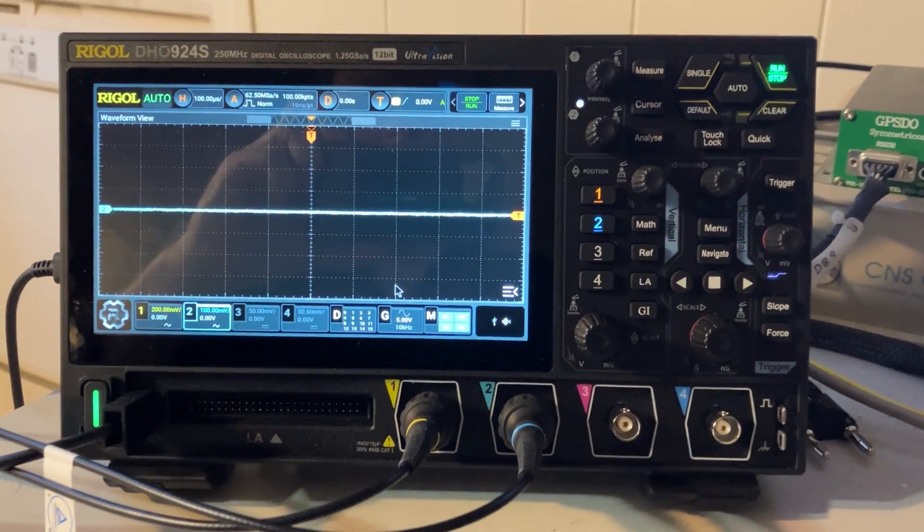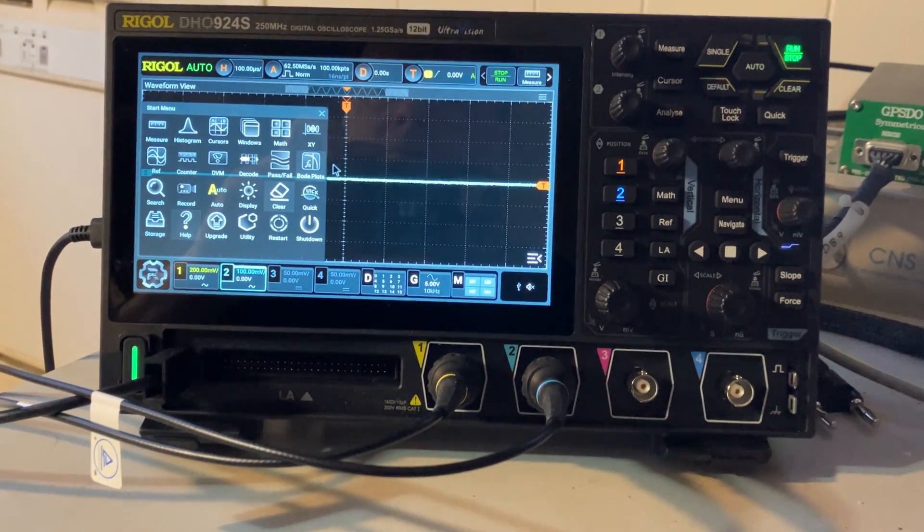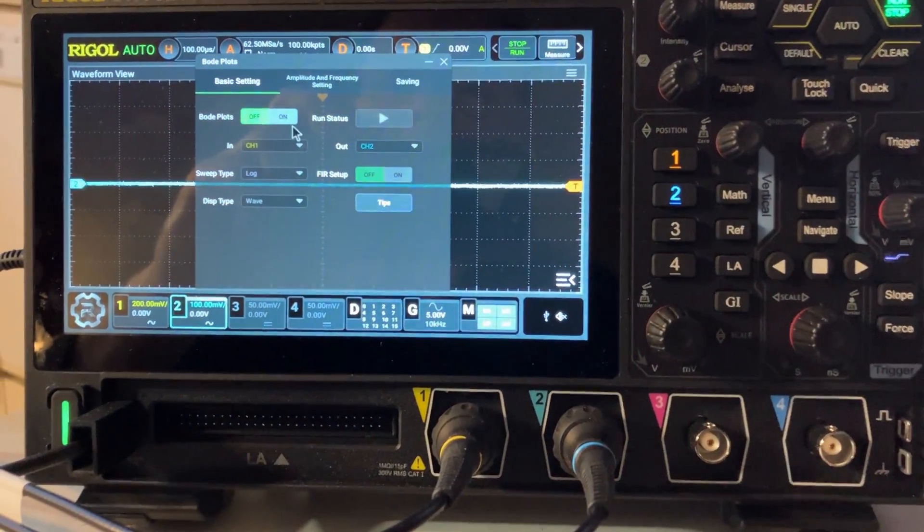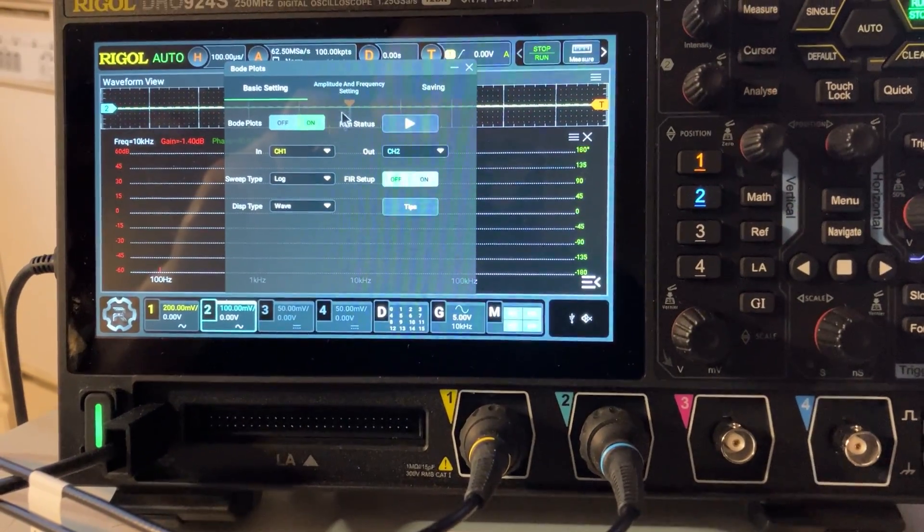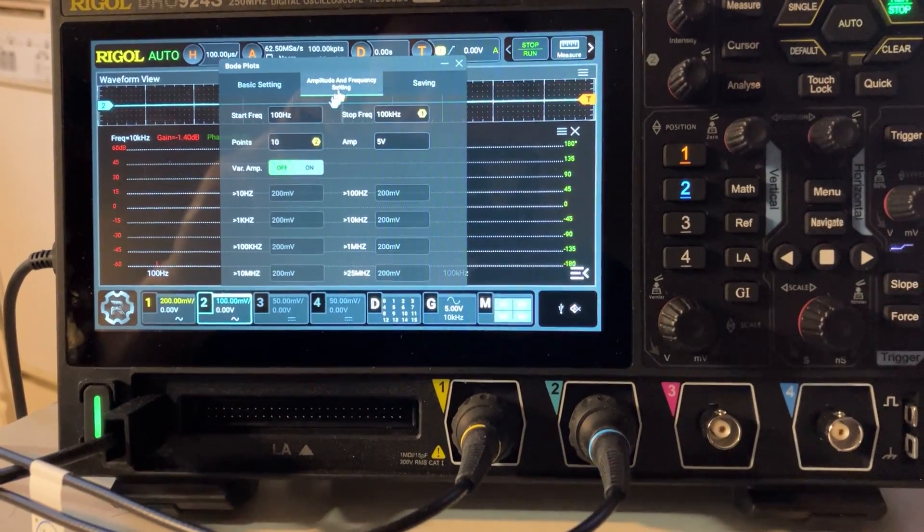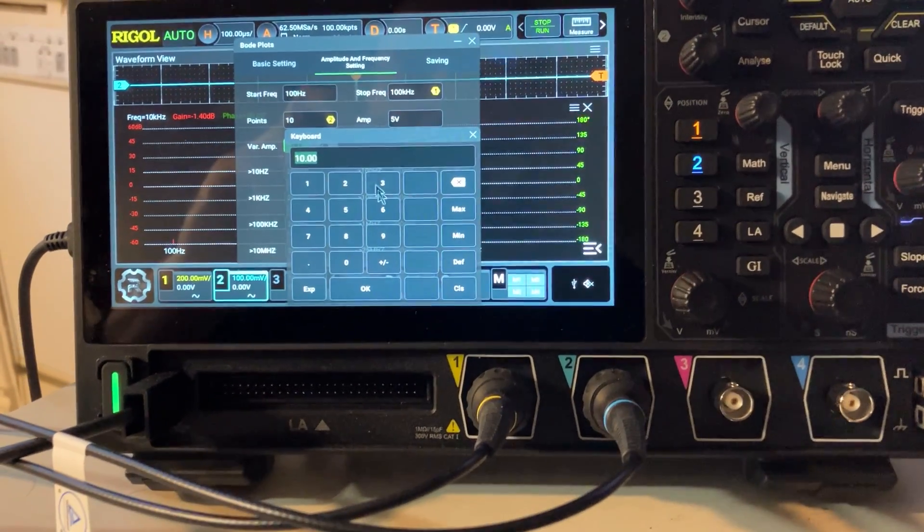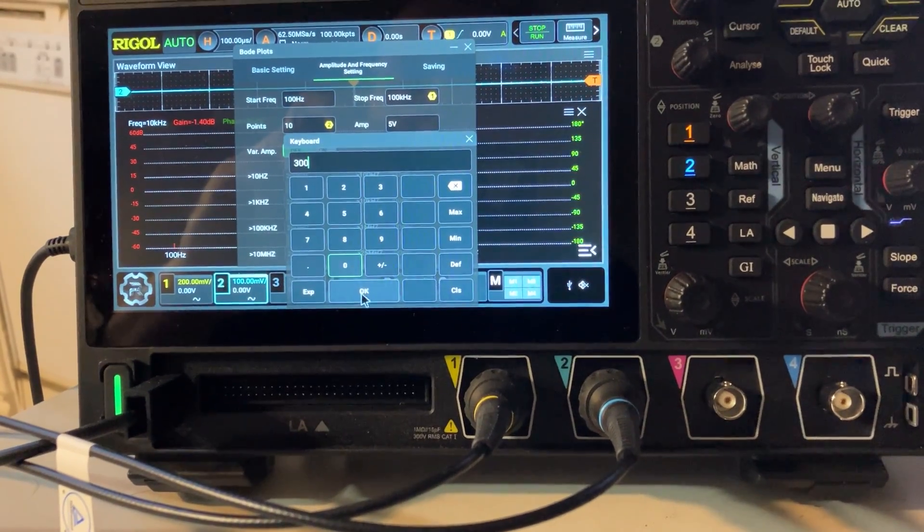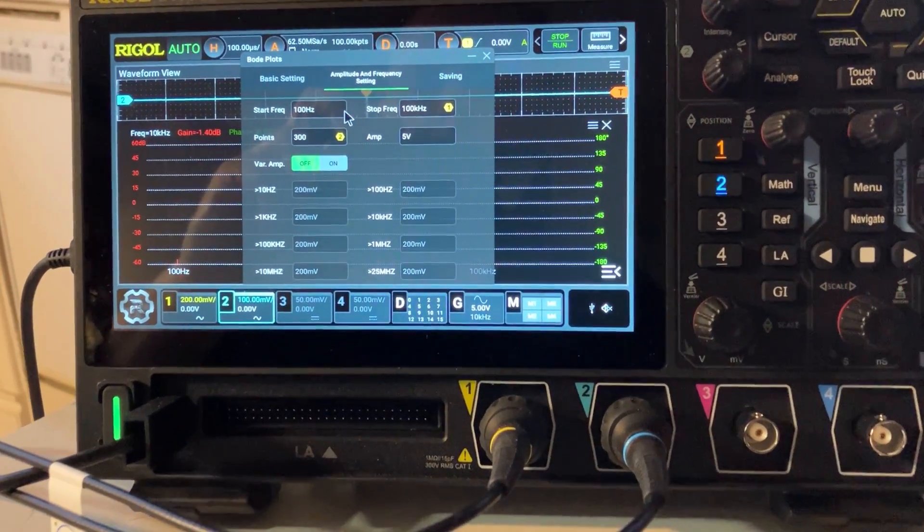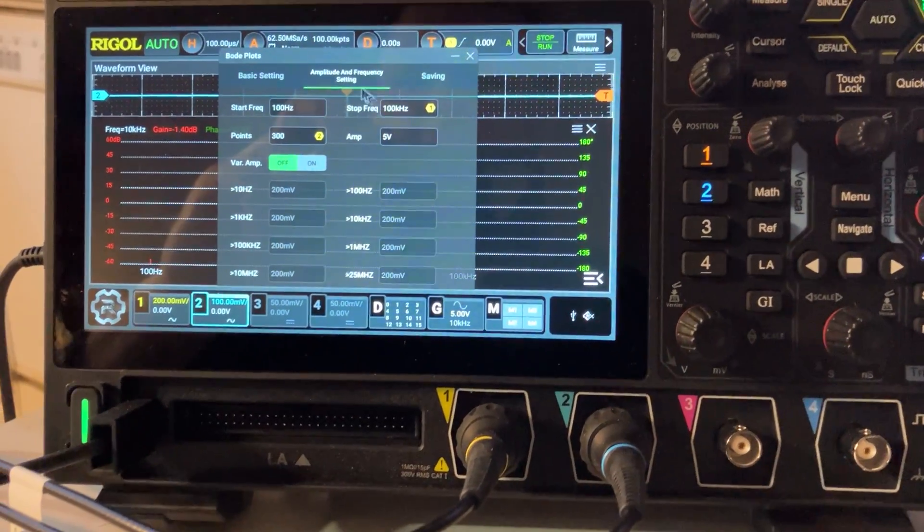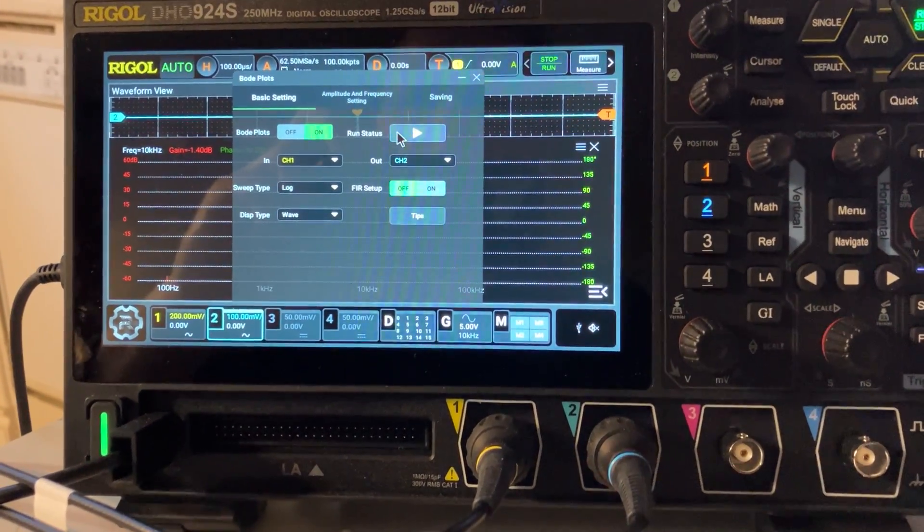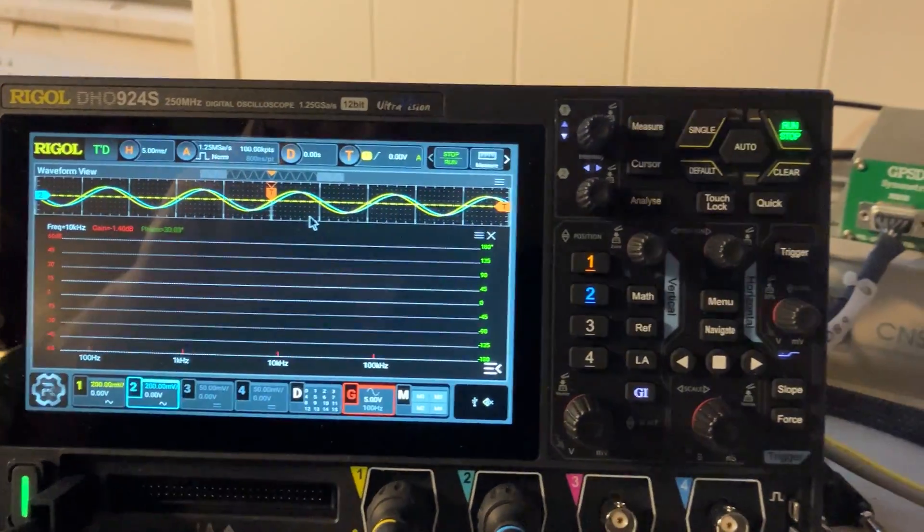One quick warning about the Bode plot - it will take over the entire scope while it analyzes, and it could take some time. Let's put the maximum here at 300 points and it will take a lot of time to acquire. Basically, the issue is while you do your acquisition, the entire scope is disabled.